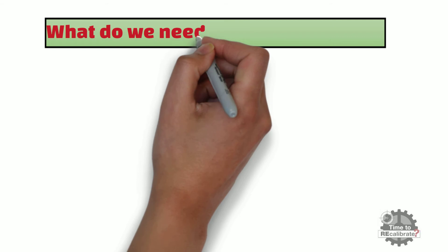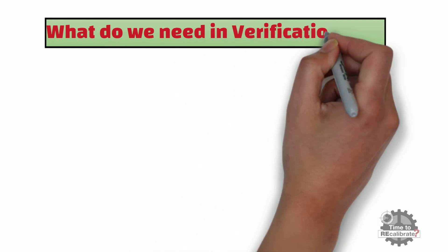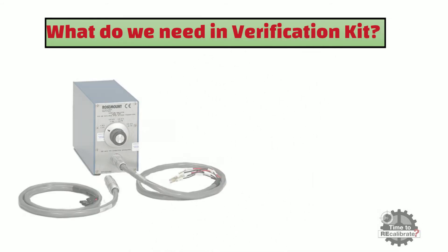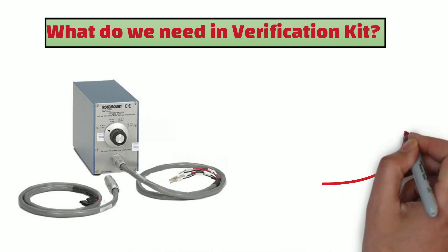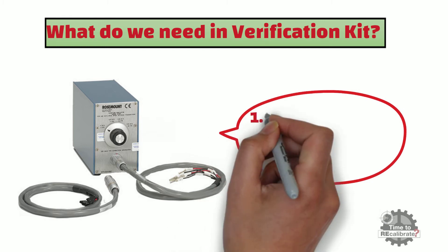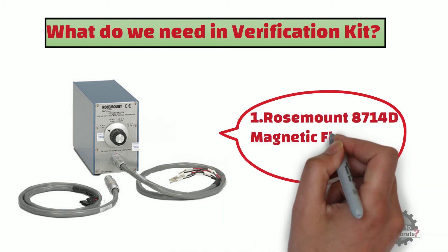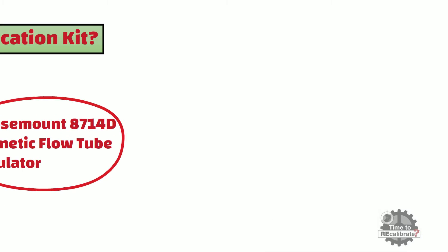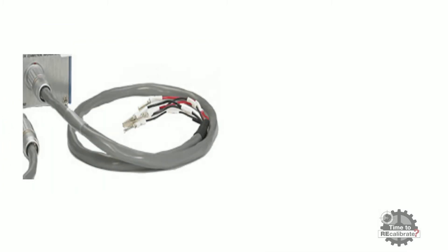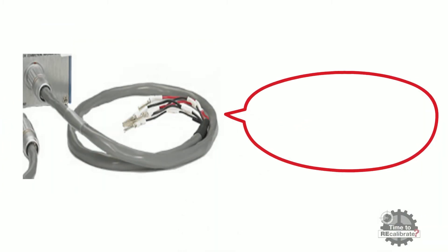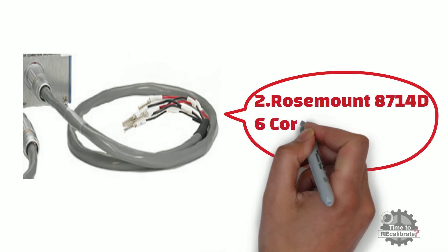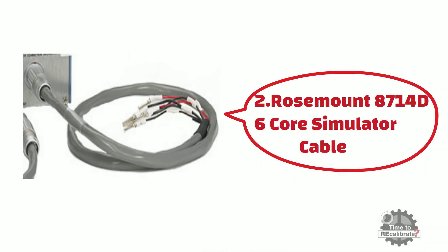First of all, what do we need in the verification kit in order to perform verification? Firstly, we need the Rosemount 8714D magnetic flow tube simulator. Secondly, we need the Rosemount 8714D six-core simulator cable. As you can see from the picture, one end has a metal connector and the other end has six cores.